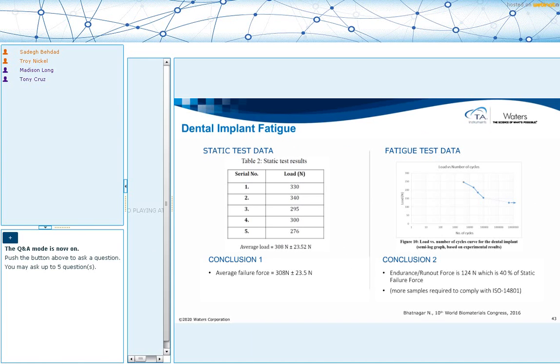So they tested 5 samples to failure, and the table on the left is showing you those 5 data points. They averaged those, and they measured that the average load to failure is going to be 308 newtons. Then they took 80% of that, so that would be the first stress level that you're testing at on the right. So this is a load of around 240 newtons. They start there. They tested a couple of samples. The samples broke, so they lowered the stress level to another one.